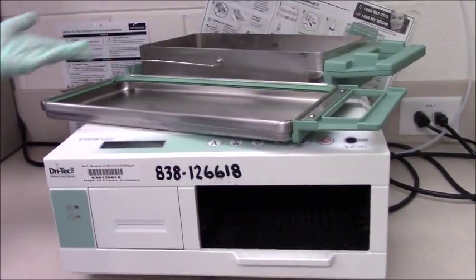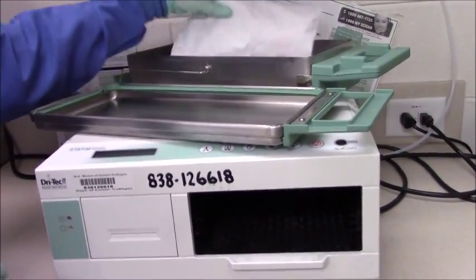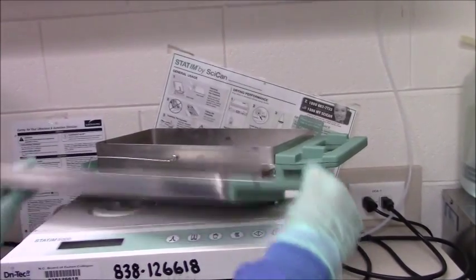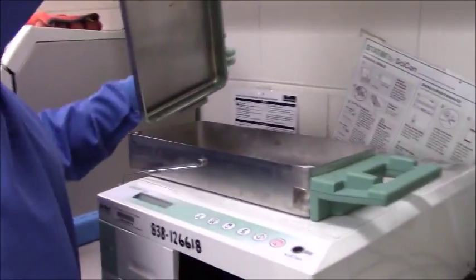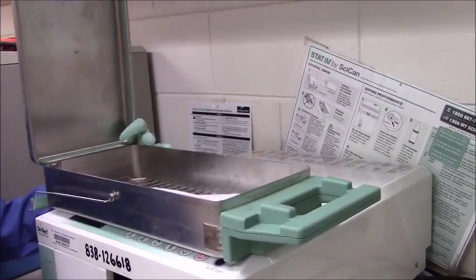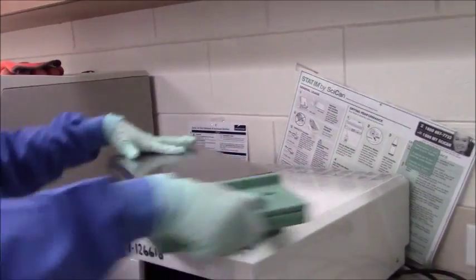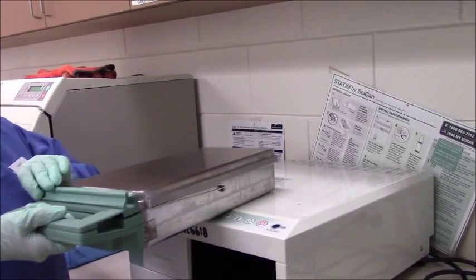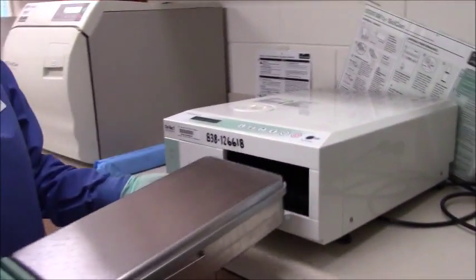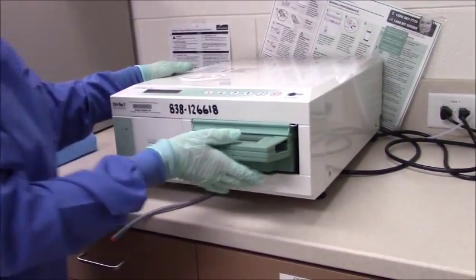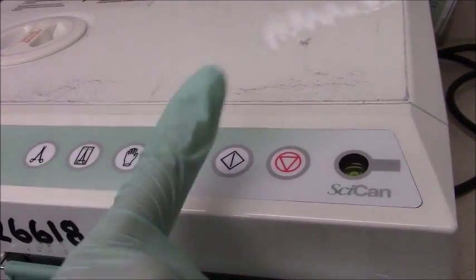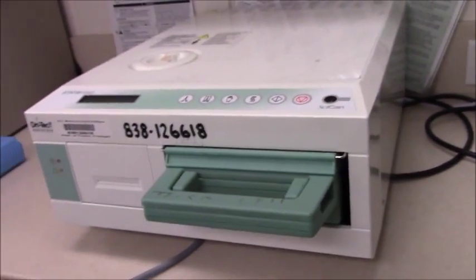Operating the Statim. Make sure all packs and bags have contents, date, and initials. Load the Statim cassette loosely, don't overload. Place the top on the Statim cassette, close until you hear a snap. Hold the cassette handle in one hand and the cassette in the other. Load the cassette into the Statim until you hear a click. Check water for proper levels. Check wastewater for proper levels. Select the proper setting. Select wrap cycle. Press start. A tone sounds when complete. If the screen displays too much water, use this tube to drain excess water.